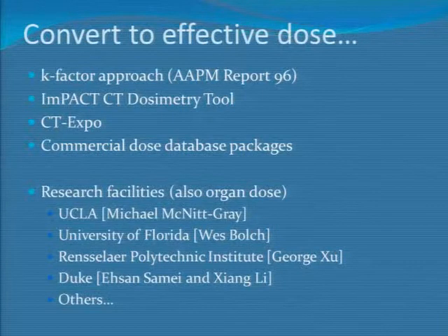So when we use effective dose, we do that from a number of different approaches. We can use the K-factor approach that's outlined in AAPM Report 96. We can use some of the online tools, including Impact and CT Expo, and now some of the commercial dose database packages will actually calculate effective dose for you automatically.